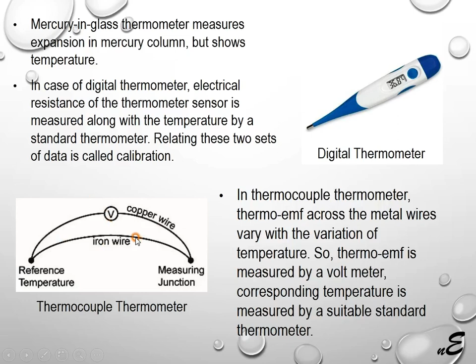If these two joints are kept at two different temperatures, the voltmeter will show a voltage called thermo EMF, related to the temperature difference between the junctions. Establishing the relationship between the thermo EMF and this temperature difference is called calibrating the thermocouple thermometer. This relationship is set as an equation in the memory of the digital system — finding this equation is called calibration.